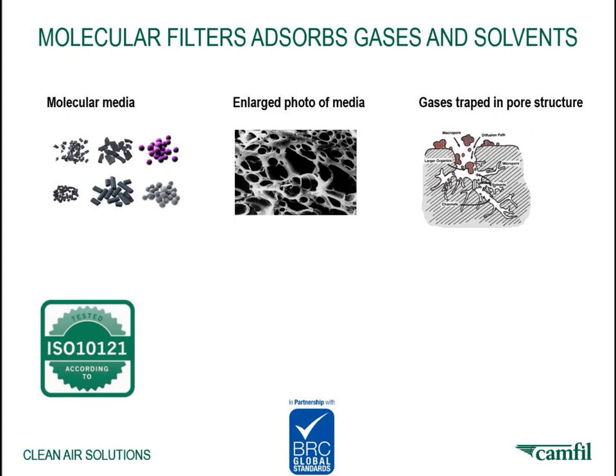We have mentioned molecular filter several times in this presentation, and this type of filter is used to remove odor, smell, or hazardous gases. Instead of mechanically filtering particles, molecular media adsorbs gases and solvents. A variety of molecular media exist depending on the target gas to trap, as you can see in the picture to the left. Just 1 gram of molecular media has up to 3,000 square meters of surface in a micropore structure, as you can see in the picture in the middle. In the final picture, we see how molecules are trapped in those micropore structures.